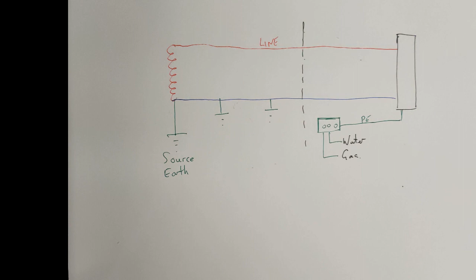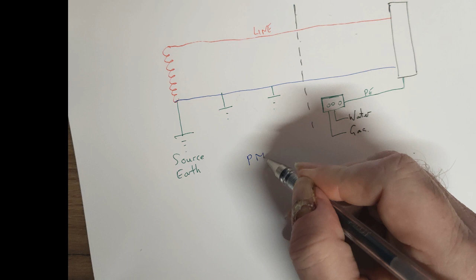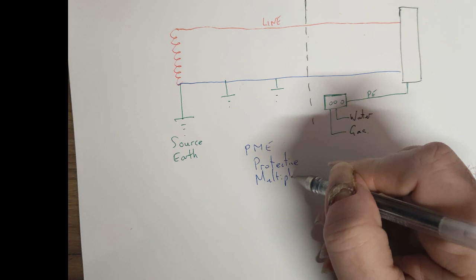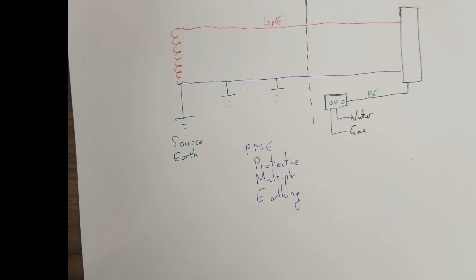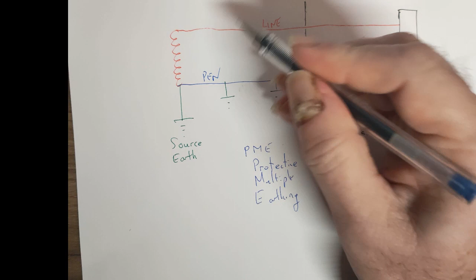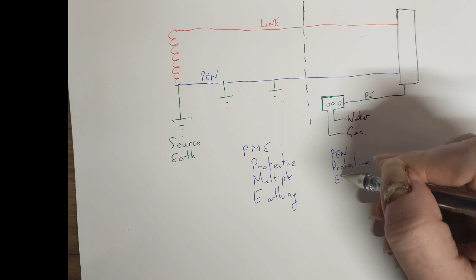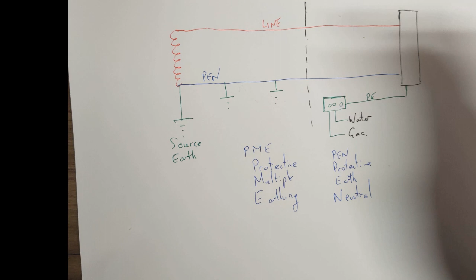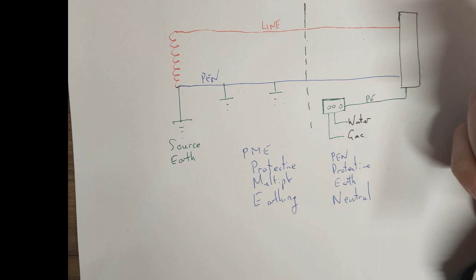Now, in a TNCS system, what you've got here, if I can grab my pens together, is also called a PME system. What that stands for is protective multiple earthing. As you can see, it's exactly what's happening. It's connected to earth in multiple points. Now this is actually called your PEN conductor, and PEN stands for protective earth neutral. So your earth is combined with the neutral line, and it splits inside your meter box.